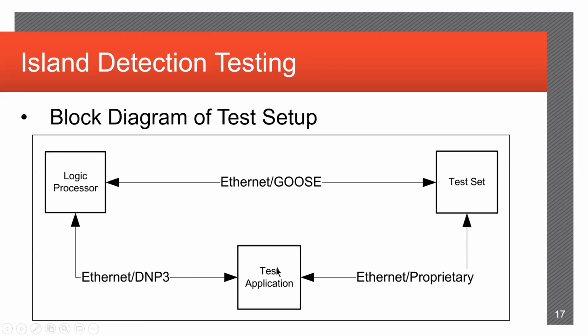So the test application itself was running on a normal run-of-the-mill Windows-based PC. It wasn't actually in a PLC. It was just on a normal laptop computer. There were actually several different protocols going on here simultaneously, all over the same Ethernet network. The test application, or the PC itself, communicated to the test set over a proprietary protocol specific to the test set itself. And then of course there was the GOOSE messaging between the test set and the logic processor. And then also the test application communicated to the logic processor over DNP3.